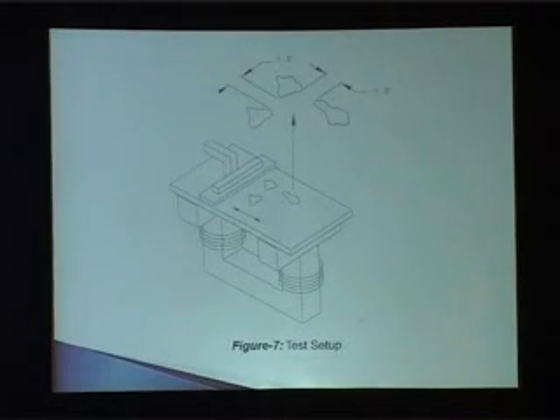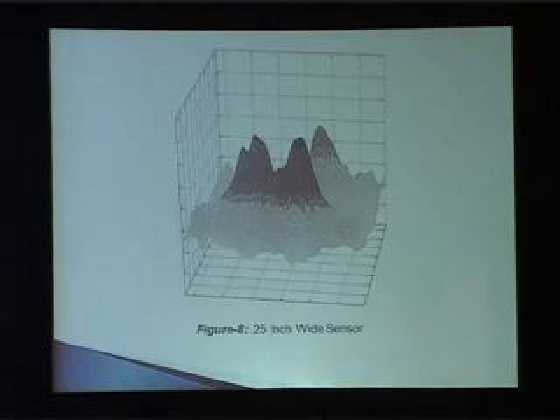These are the 3 defects. Okay, and this is the setup. This is the test setup which was used. The distance between them is 1.2 inches as shown here. And as a result of running one with 0.25 inch wide sensors, the width of the sensor is only a quarter of an inch, that is around 6 millimeters, you get these types of peaks for the 3 defects.